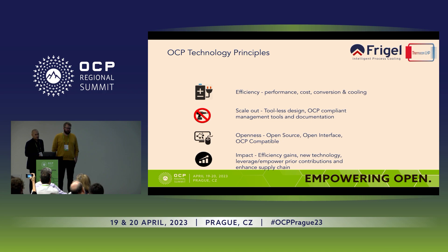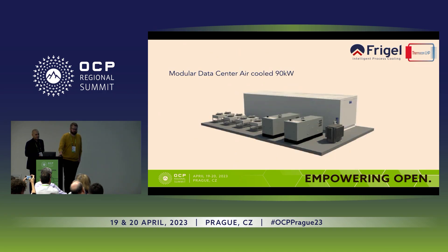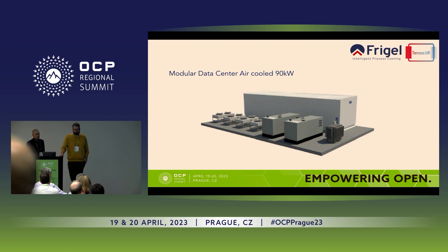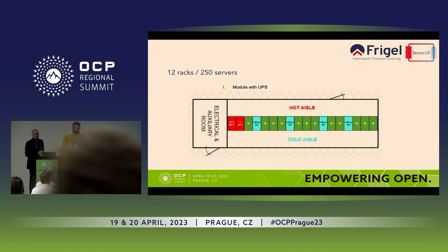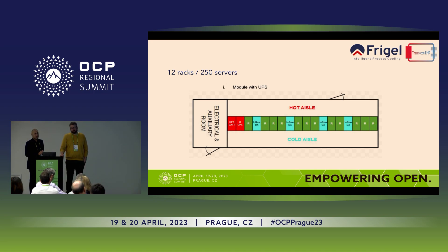The principles are: toolless, efficient. Now we want to show what we have already in OCP. An example is a 90-kilowatt modular data center, which is air-cooled. The bottleneck is the air coolers, which are limited to 90 kilowatts. For that reason, the 12 racks are half empty — each one has 7 in use instead of 14. But we can place 250 servers.